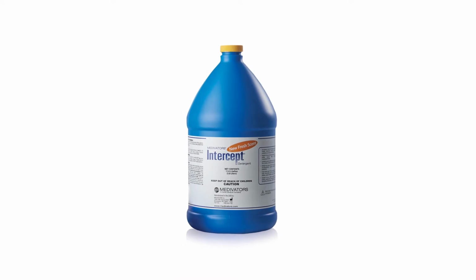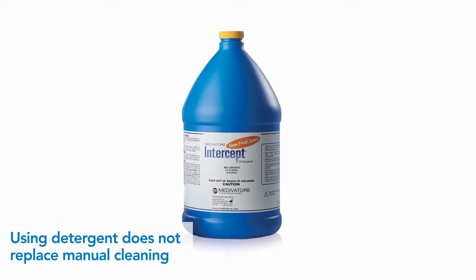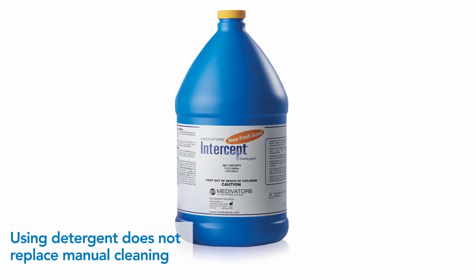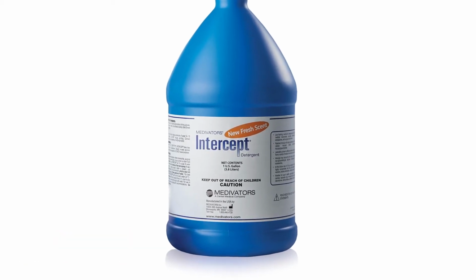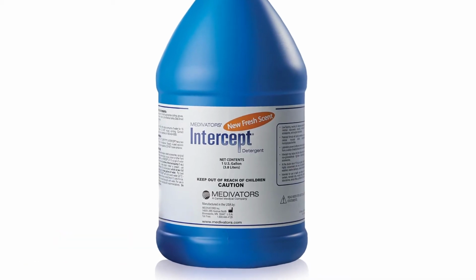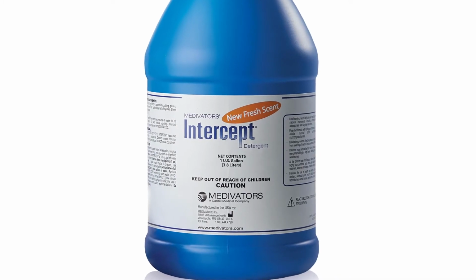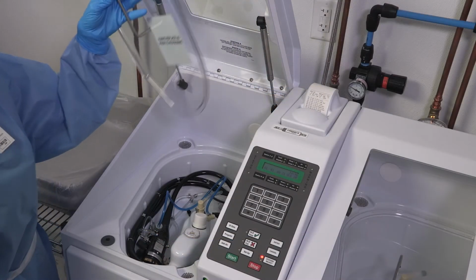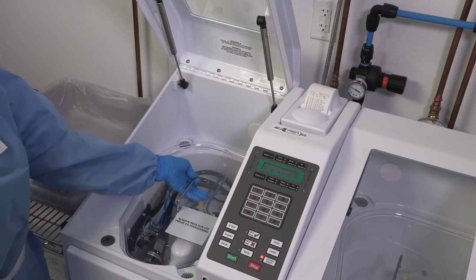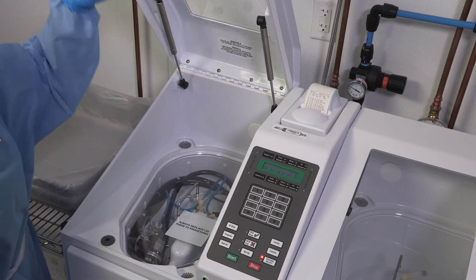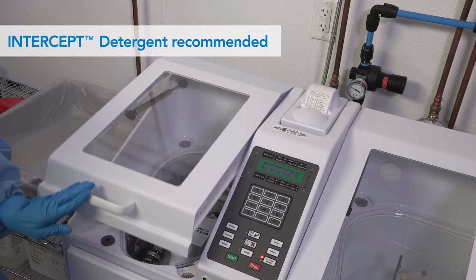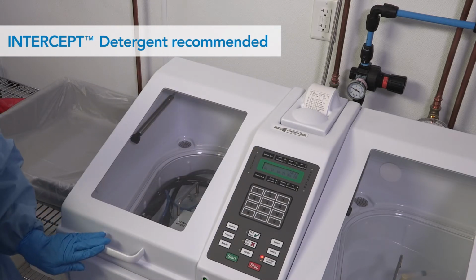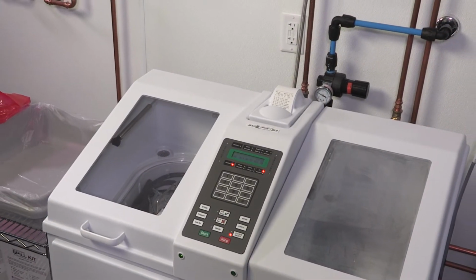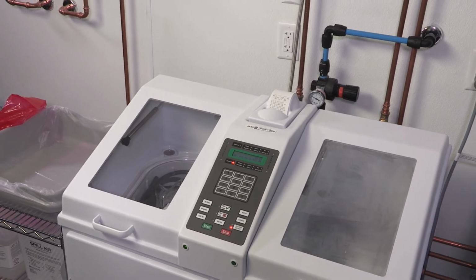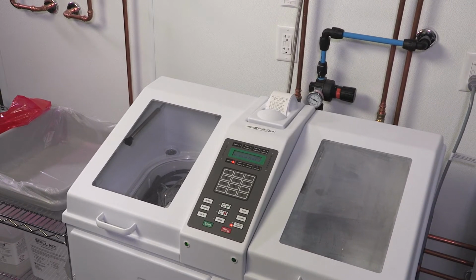Using detergent in the DSD EDGE Reprocessor does not replace any of the required steps in manual cleaning. Every step in the manual cleaning process must be completed whether the detergent phase is used or not. If your facility uses the AER pre-wash function in the reprocessing cycle, Cantel recommends the use of Intercept detergent, which has bacteriostatic properties to inhibit bacterial growth in the detergent reservoir and detergent line. It is recommended and validated for use in the DSD EDGE Reprocessor.